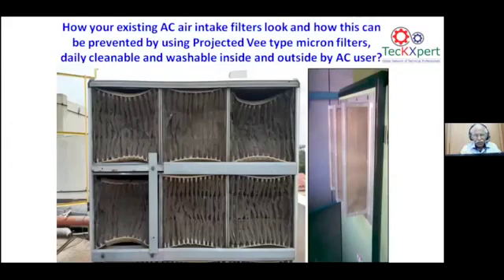this area. It is put on the open terrace. Everyone ignores it. Let us try to have what I was telling you, a 3-tier system. Let us have a V-type filter. Let us have a 10 micron filter. Then we can hope for a HEPA filter. Definitely this type of abnormal deviation, especially total choking of this filter, and the pressure problem, will not happen. The indoor air quality of a given premises drops totally because of this pressure on the filter. This can be corrected as such.